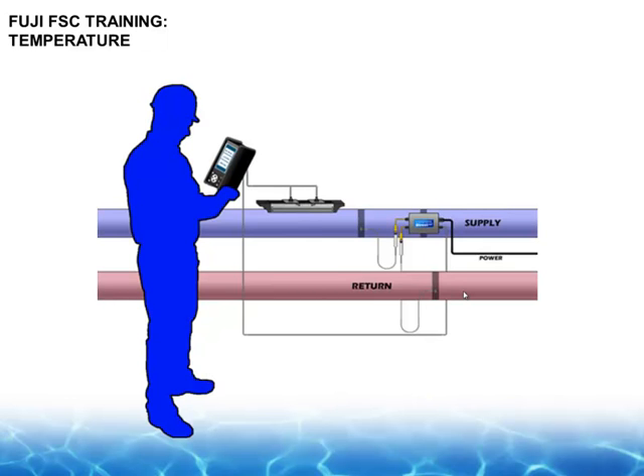Temperature is a hot potato. If you lived in Europe, you may get the bill for your apartment or flat in BTU. They've culminated everything together, and when everything's all together, people tend to spend less money. And so everybody that's in the university business or large facility business or large office complex business wants to know their energy consumption. And the way they do that with the Fuji meter is we'll take the portable meter and we'll clamp a sensor on the supply line. Now the supply and the return line are in a closed loop, so the flow is the same in the facility itself there. So we only need to monitor once.